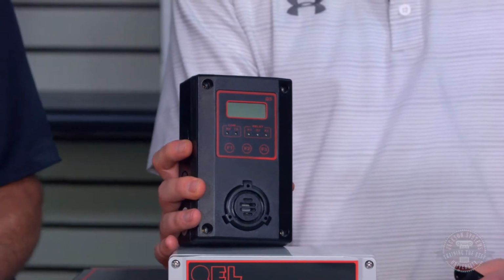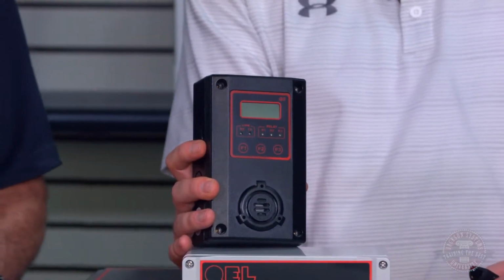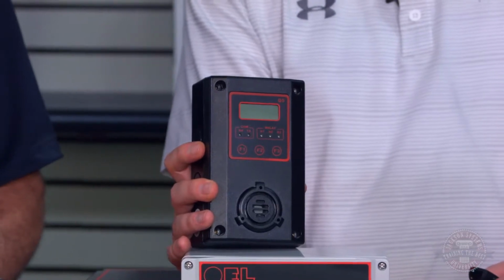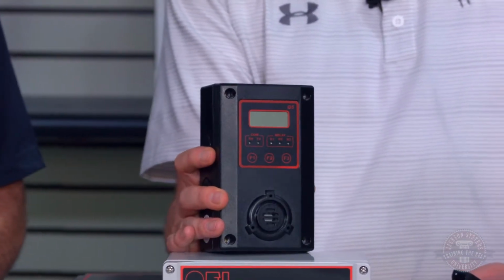The difference is that if you look at this sensor, I don't know, Tyler, can you zoom in on that? Or Alex? If you zoom in on that sensor, you'll see where the lights are. They're right here. That is meeting the spec of a visual alarm. You can't see that from across the room, but that is meeting the spec. The horn in here is about 70 decibels. If you're in a warehouse, you can't hear that. It's not loud enough. But you can hear that one.